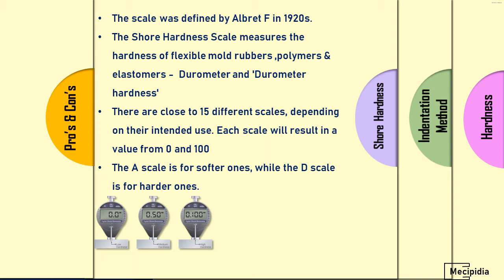A scale is used for softer materials and D scale for harder materials. You can see the configuration of A and D scales - both are applied by manual force. A scale has a 35-degree cone tip with 1.4mm diameter and 8 Newton load. D scale has a 30-degree cone, same 1.4mm diameter, and load up to 44.45 Newton.